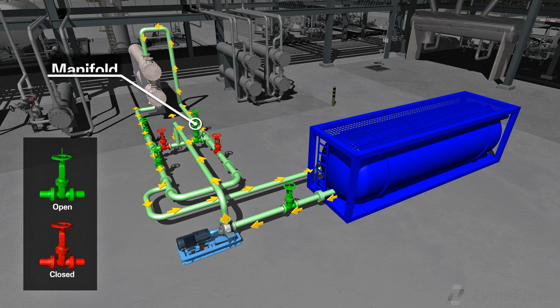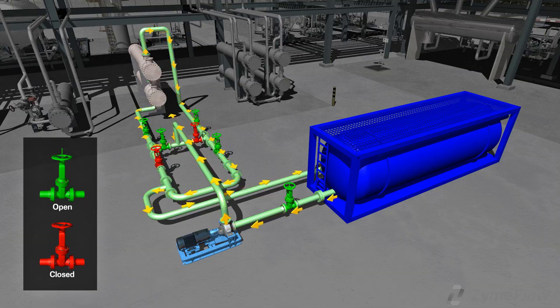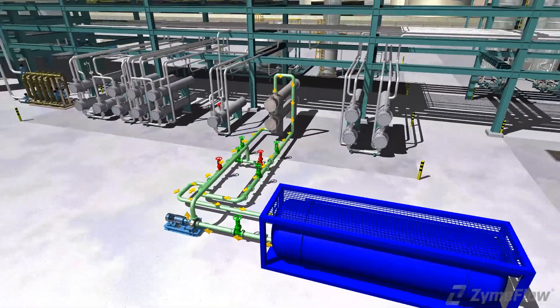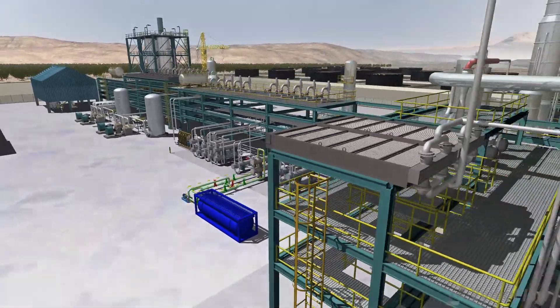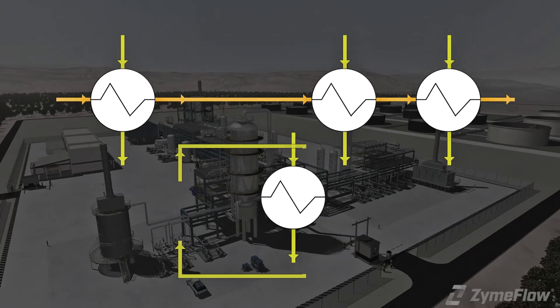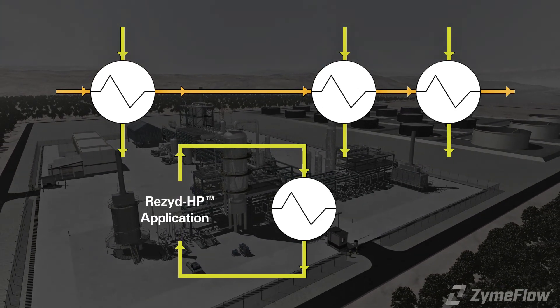A special manifold has a series of isolation valves that allows the flow direction through the exchangers to be reversed, increasing the efficiency of the process. If needed, the procedure can be performed while the unit remains online by only temporarily bypassing one segment of the exchanger group. Therefore, partial efficiency can be regained between turnarounds while the process unit can stay in service.